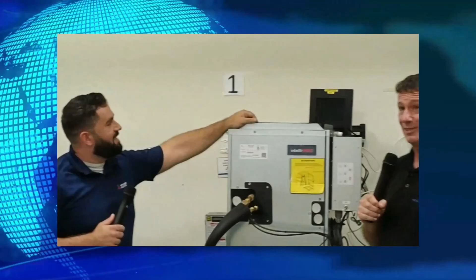What I love about this particular system is our capacity balance point as well as our economic balance point. It has an algorithm with learning capability where we set an initial balance point, just like any other cased coil, based on temperature. But it also has learning built in that will, if we start to lose comfort maintaining space temperature after about 24 minutes, start staging that gas. So unlike a typical heat pump where you need set points or something configured through the thermostat, it's all built into the system, so we don't need any of the traditional thermostat wiring.